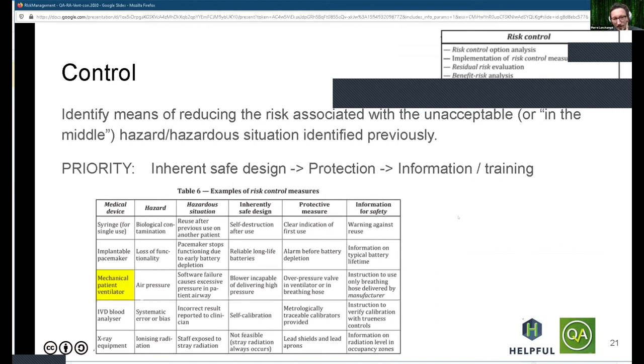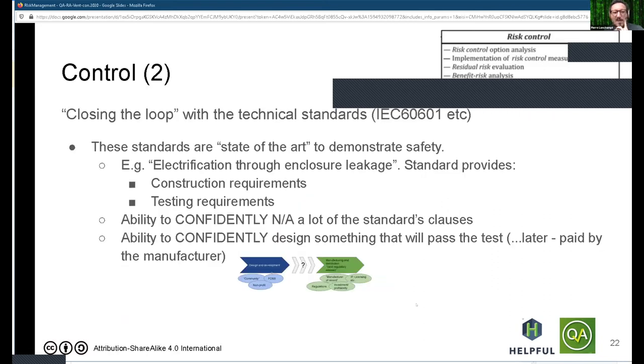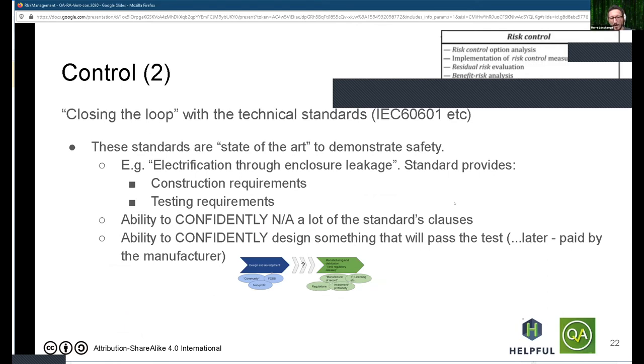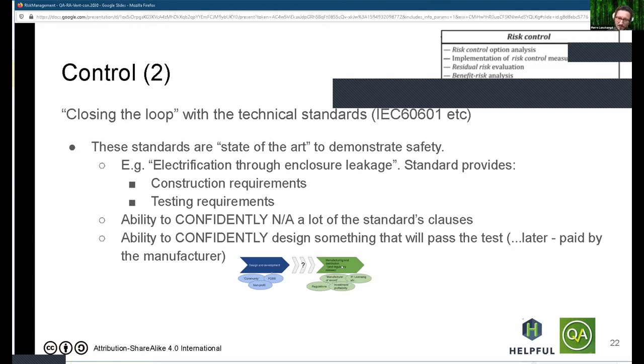You always want to favor inherently safe design rather than protective measures, information, and training. There's a great example in TR 24971 about mechanical ventilators. Technical standards also come back into play as great risk controls — for instance, if you're working on an electrical device, you want to ensure you're not electrifying your users, and 60601 gives you both construction and testing requirements. In the open source context, we may not have resources to test to 60601 in a proper lab, but having the construction requirements gives us confidence we're likely to pass the test later when a manufacturer is willing to pay for it.